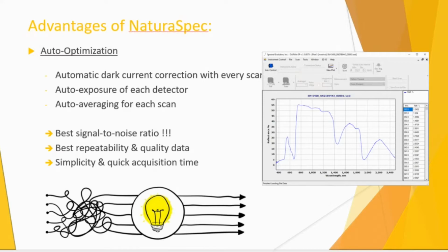As far as the averaging for each scan, we have two modes for that. You can either tell the instrument to automatically take the optimum number of averages for each detector. What an average is, is that when we take a measurement, it's actually an average of several measurements. So it's not just one scan and we're done. It's like 10 scans, 20 scans, or 40 scans. And the reason for that is that the more data you get, the better statistical distribution of the signal and a better average, and a better approach of the signal to what you're really measuring.